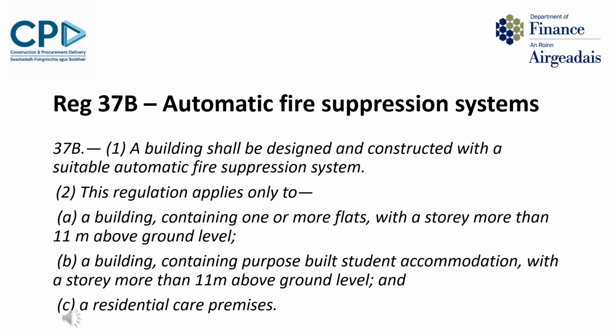The other new regulation in Part E is 37B, Automatic Fire Suppression Systems. So 37B1 requires a building to be designed and constructed with a suitable automatic fire suppression system. 37B2 lists in a prescriptive way the limitation of the requirement to specific building types. Those types are A, a building containing one or more flats with a storey more than 11 metres above ground level. B, a building containing purpose-built student accommodation with a storey more than 11 metres above ground level. And C, residential care premises.